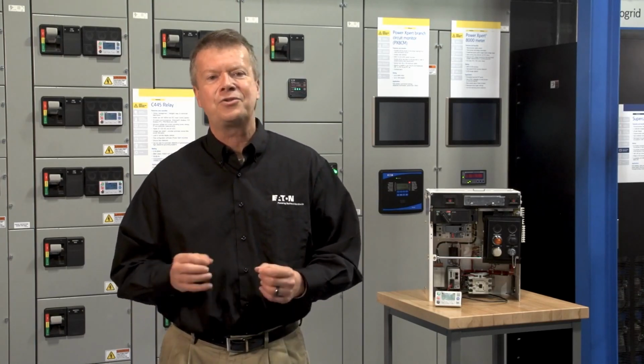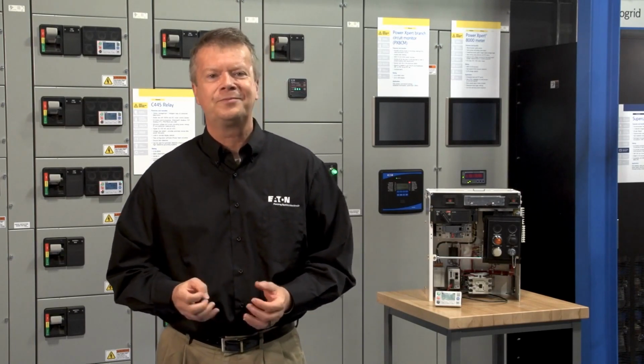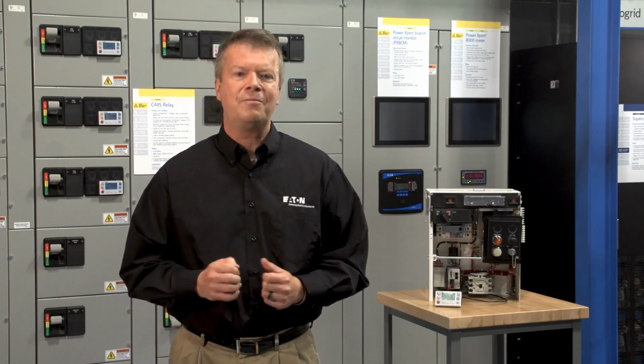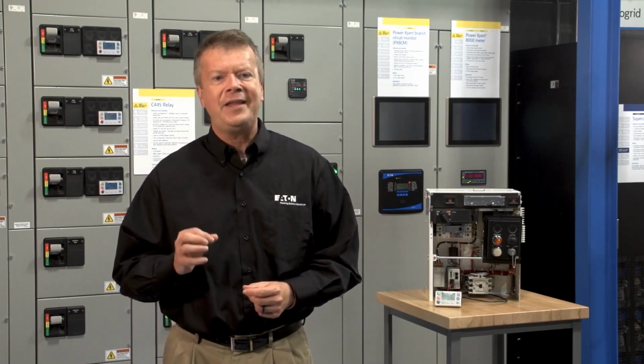Latch contactors use a stored energy mechanism similar to the spring used to open a circuit breaker. A reliable source of power must be available to operate the solenoid that opens the latch contactor in the absence of control voltage. Capacitor trip devices, as are used with stored energy breakers, are commonly available to solve this problem. A latch contactor may last for tens of thousands of operations. If the load is infrequently switched, consider latch contactors.